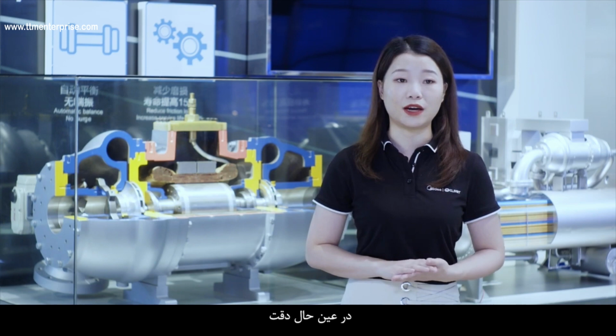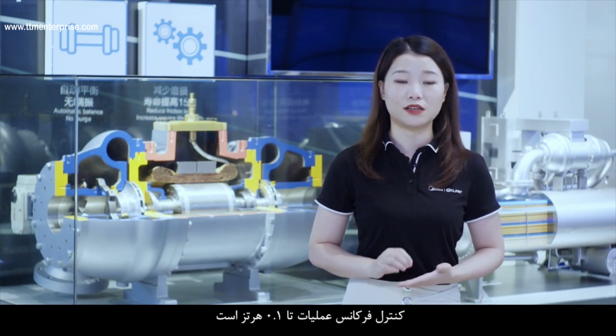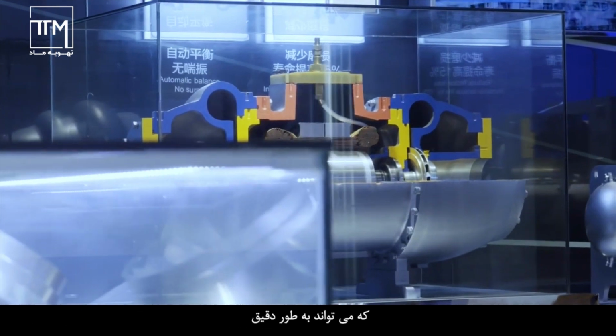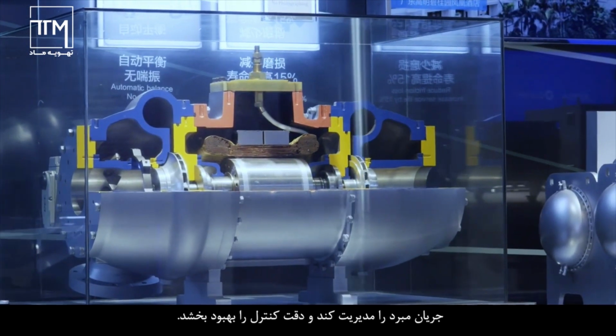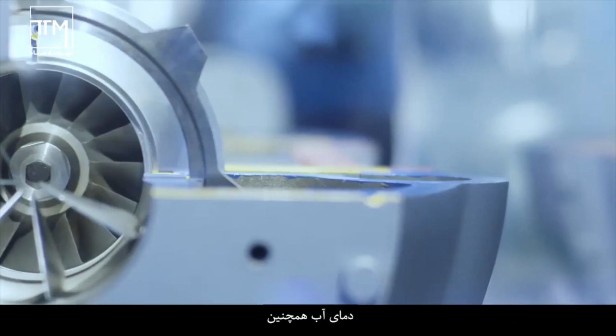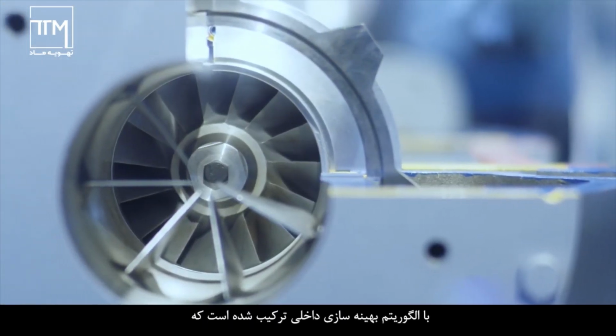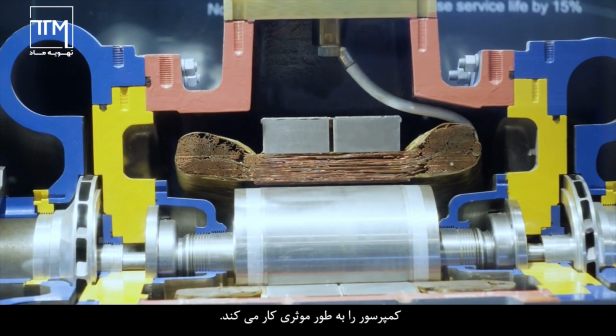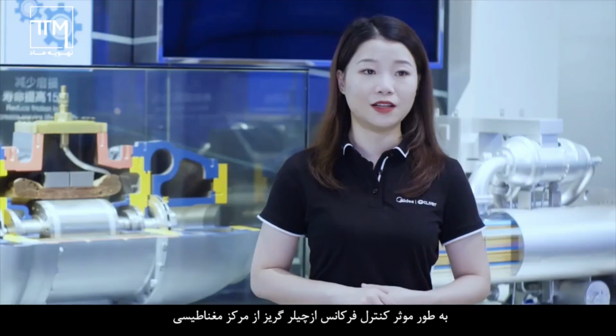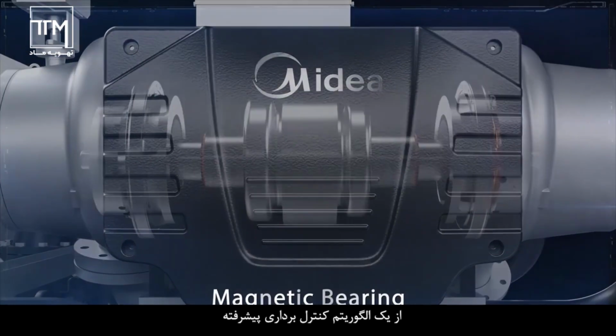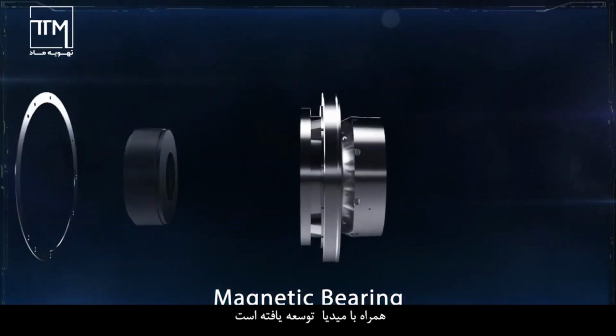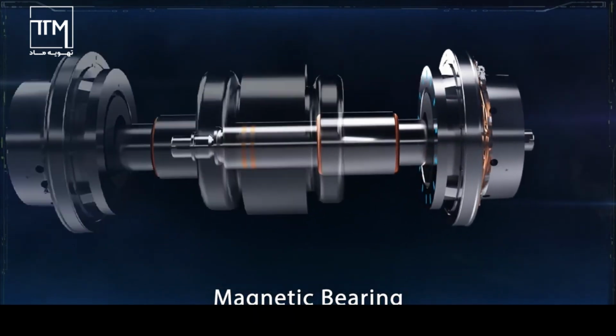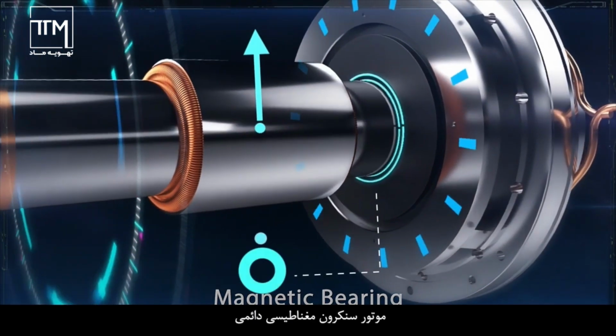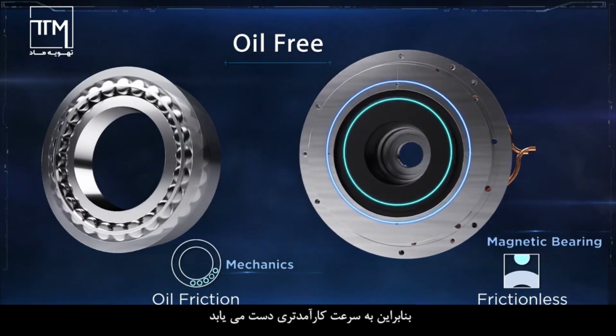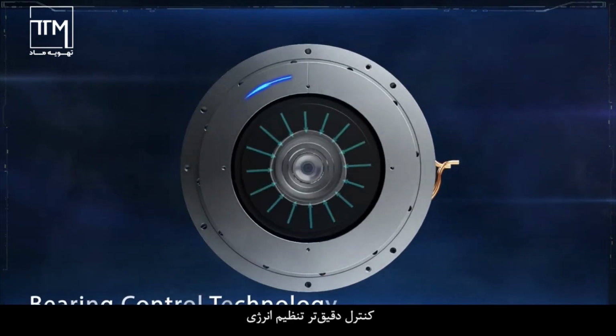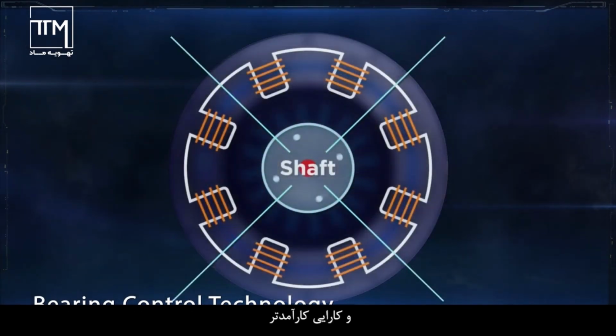Meanwhile, the accuracy of the operation frequency control is up to 0.1 Hz, which can precisely manage the refrigerant flow and improve the control accuracy of water temperature. It also combined with the built-in optimization algorithm, keeping the compressor running efficiently. The frequency control of the magnetic centrifugal chiller uses an advanced vector control algorithm and is combined with Midea's self-developed permanent magnetic synchronous motor. Thus achieves a more efficient speed control, making energy regulation more accurate and operating more efficient.